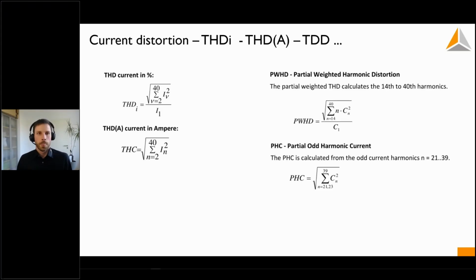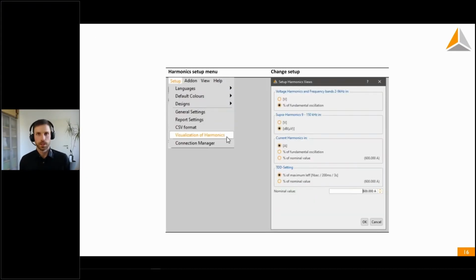considered. Very important: if you open harmonics and display them in the level time, in the timing diagram, for example, and see the THD over a week or the 15th harmonic over a week, you can select whether you want to see the values in percent of the fundamental oscillation, or in percent of a nominal value. Then you can change the nominal value, of course, in amps. You can change the nominal value in these settings in the harmonic view as well. So you can change the view in here in the settings.